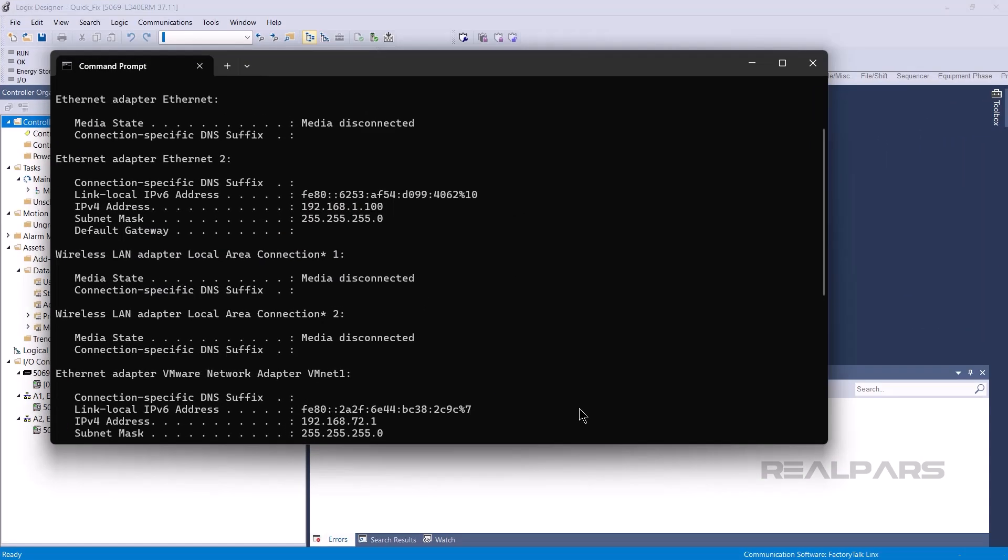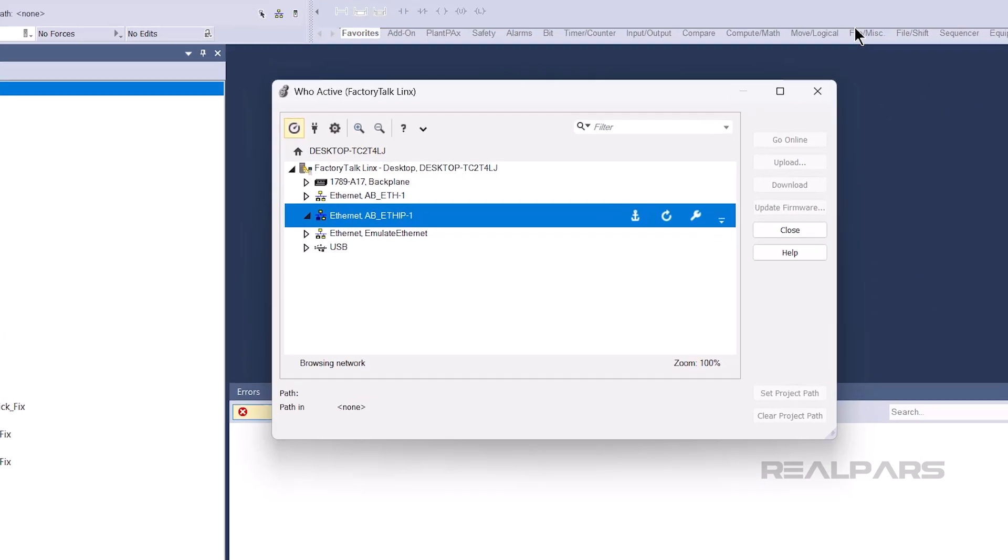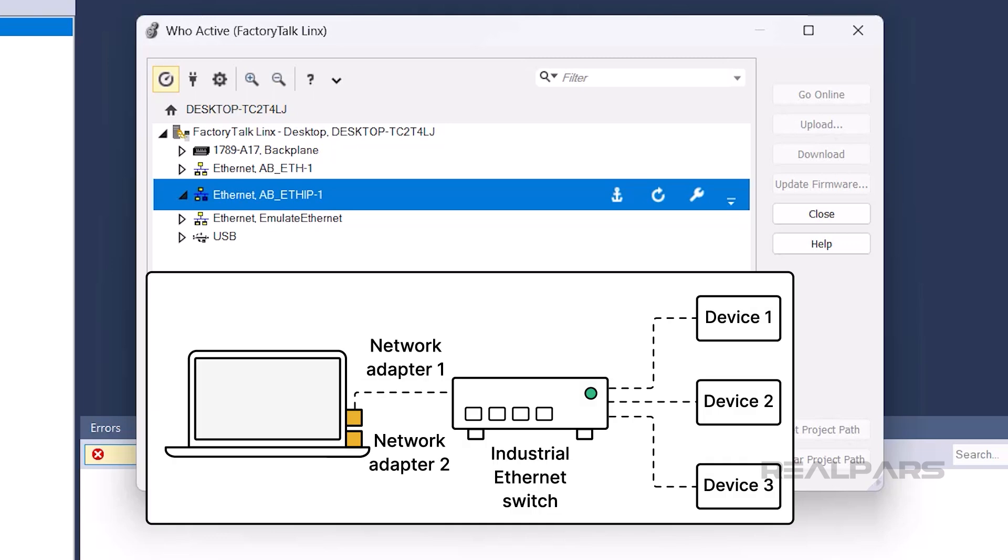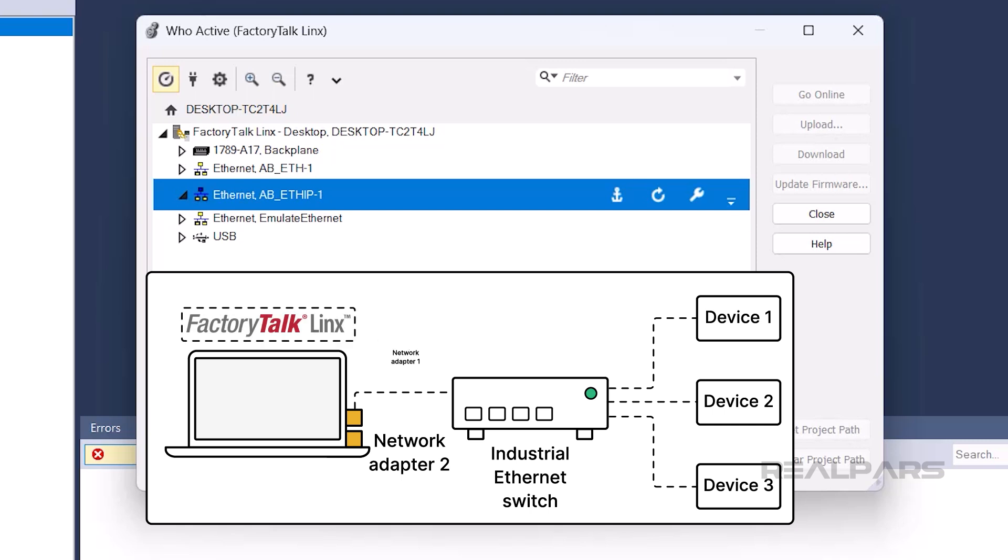If the IP address of your computer is correct, the issue may be that the driver is using the wrong network adapter to send broadcast messages. By default, FactoryTalk Linx uses the Windows default adapter, which can be the Ethernet or Wi-Fi card.